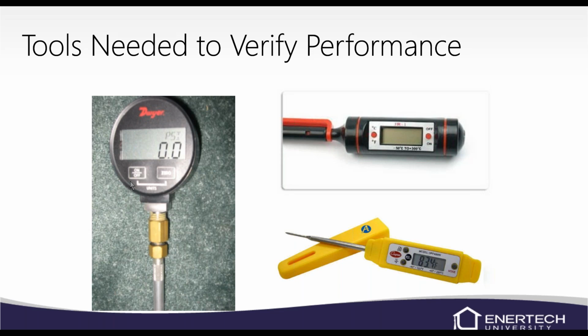These are the tools that I would recommend. This is a digital pressure gauge made by Dwyer. We do sell it at Enertech. You can also purchase it online. If you purchase it online, make sure to get the needle as well to go into the pressure temperature port. If you order one from Enertech, customer service is usually pretty good about asking you. And we've got the needles that are real thin, so they go into the PT ports a lot better. If you buy one of those needles at the hardware store, a lot of times they're real thick, and so they don't really want to go into the PT port very easily.